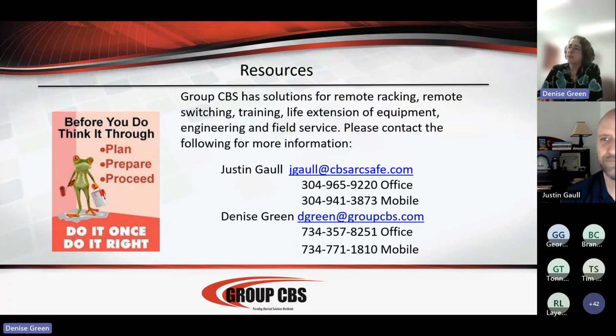Right. So NETA is the National Electric Testing Association, international, but they use the N. And they have developed 2 standards. One is maintenance testing standard, which is MTS, and they have an ATS, which is acceptance testing standard. So there are different test parameters for new equipment, and that's what acceptance testing is. And then their MTS, which is their maintenance testing standard, is for existing equipment. So that NETA MTS goes hand in hand with the NFPA 70B on electrical testing of equipment and what you should be doing.